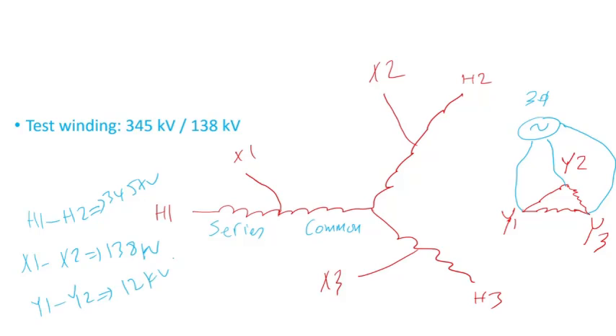For this auto transformer with a test winding: H1 to H2 is 345 kV, X1 to X2 is 138 kV, and Y1 to Y2 is whatever the manufacturer designed — for instance 12 kV. The series winding, common winding, and test winding are all wound around the same core, so they all see the same flux. When you apply voltage to the test winding, that flux links the common and series windings — that's how the test is performed under this condition.